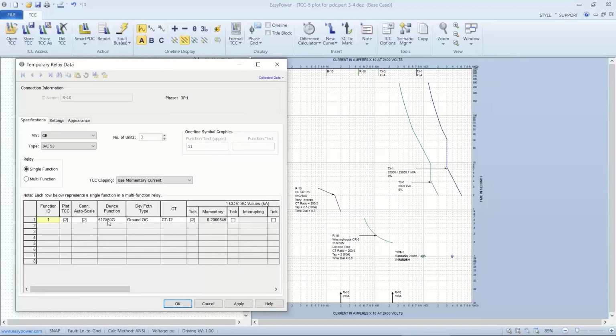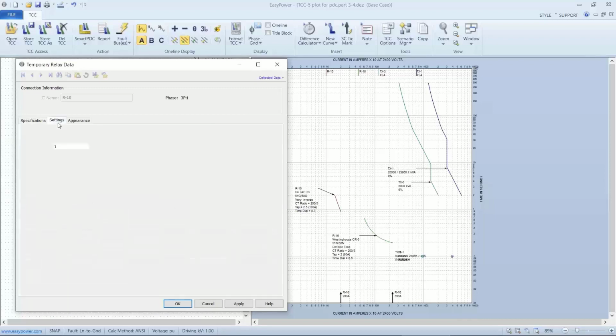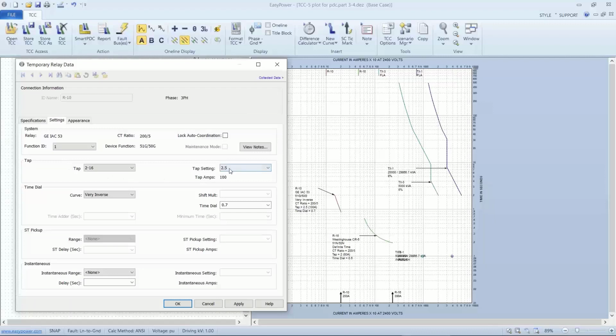we want to make sure that the device function matches the function type, because this can be a little bit of an issue if you don't pick out the right selection. And then when we go to settings on trip 1, we have it set up for pickup at 100 amps and then a decreasing or very inverse trip time according to the dial. And again, these can have instantaneous trip settings based upon the delay. Let's see if we can show it. So it makes a steeper curve, and we'd want to set it inside the limit.